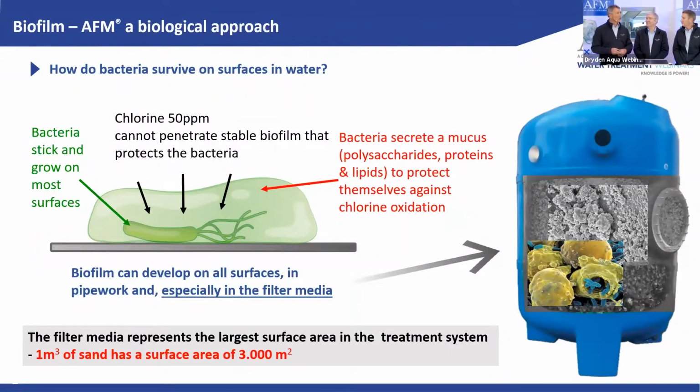But also, you know, this is what we talked about. Very often you say, well, I have to chlorinate the sand filter to keep it free of bacteria. That will not work. Often you see over a certain period of time, over years, that chlorinated systems, especially if they are chlorinated at the same level, get an even bigger biofilm problem than a low or non-chlorinated system. Through this process of natural selection, you kill the weak bugs and you leave the room to the strong bugs. That's very important.